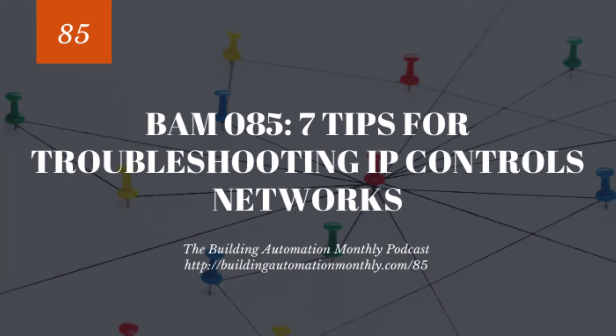But the bigger one is BBMDs. Basically, a BACnet Broadcast Management Device consists of a table of network segments that have BACnet devices on them. Essentially, you need to populate those tables so that the devices know where to communicate. But you also need to have a BBMD in each network segment to forward traffic, because BACnet is a broadcast protocol, meaning that it uses messages like Who-Is, I-Am, those kinds of things, and they get broadcast across the network. Well, broadcasts can't leave subnets.